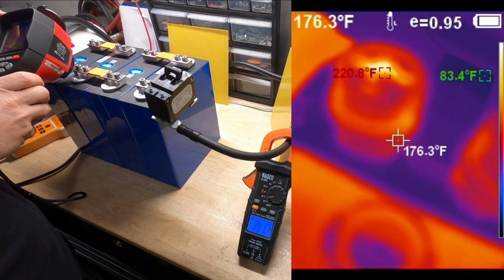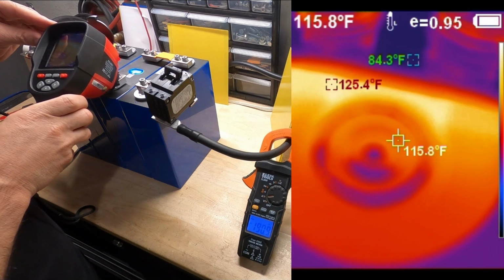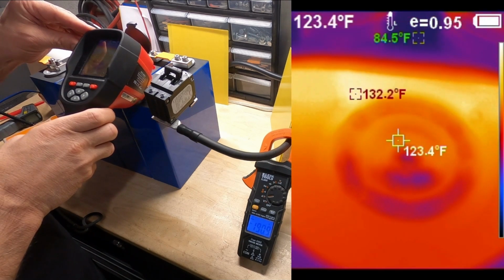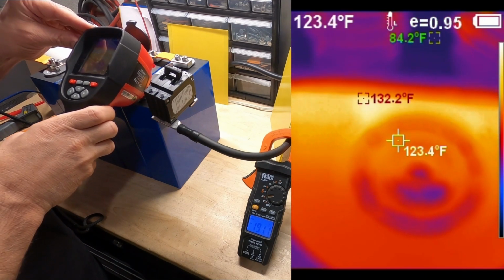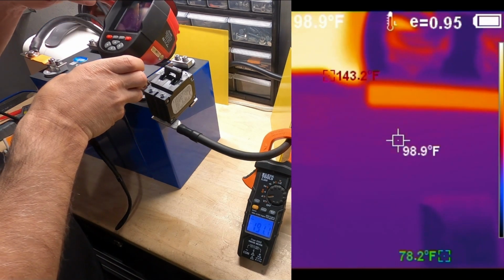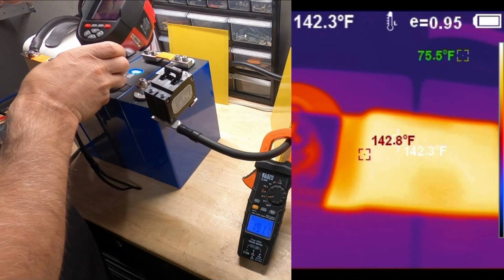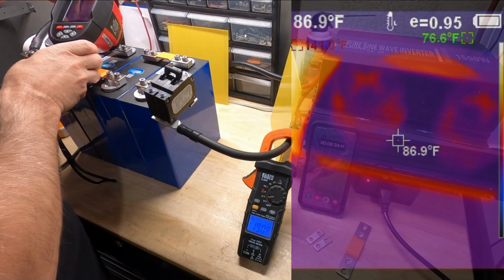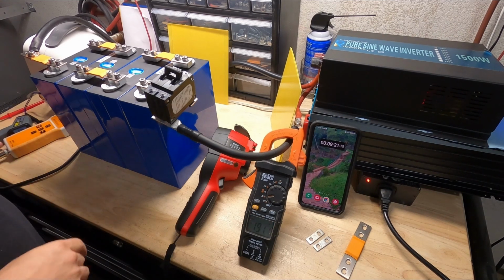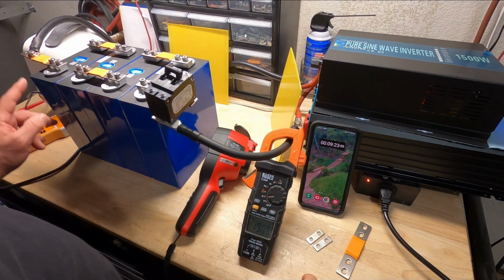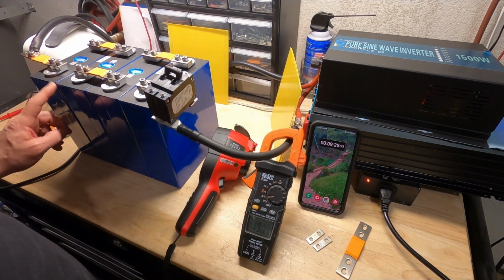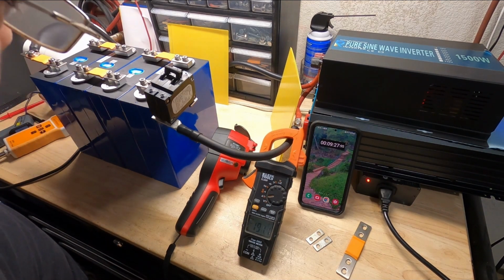That is crazy. 125. 132. That's the one with the breaker, so it's going to be warmer. That one's pushing 140. Anyway, I'm going to stop the test, and then we're going to swap out this one cell and see if we can resolve this issue.